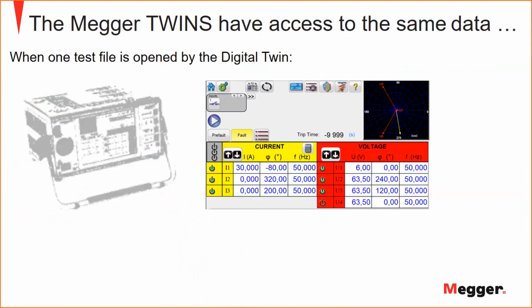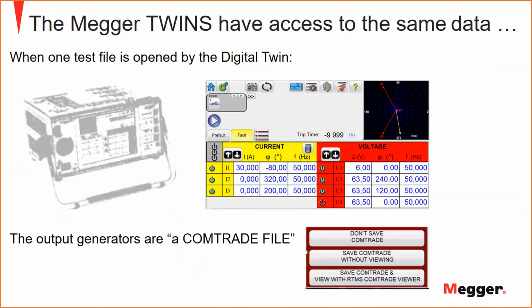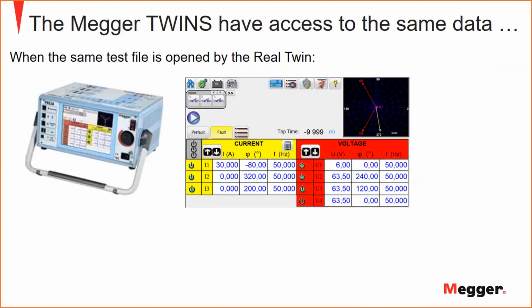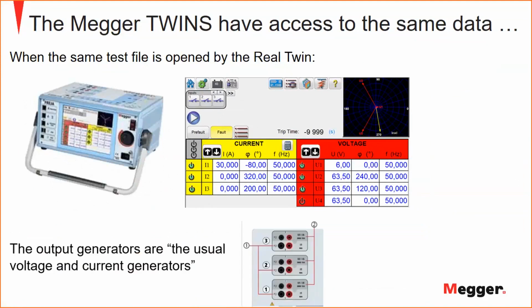When one test file is opened by the digital twin, the output generator is at the moment a COMTRADE file. When the same file is opened by the real test set, the output generators are the usual voltage and current generators. So I want you to understand this because it's important. It has to do with the fact that the twins have access to the same data.